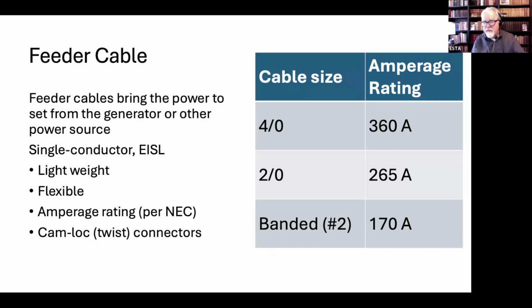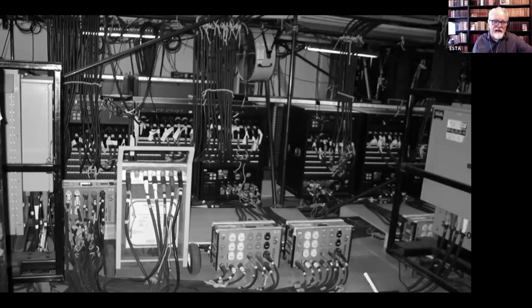With the 4-aught, we'd have more than 1,000 amps available to us at the destination. So we get to the set, and this is a very complicated set, but the feeder cables are going to terminate at these 2 boxes at the bottom center of the picture, which are spider boxes. It could also feed, this is an older picture, so there's a lot of dimmer racks in the background. There's also a GFI unit, this giant thing on the left. And there's 2 transformers on the far left and right side of the screen, which are actually 480, 208 transformers.